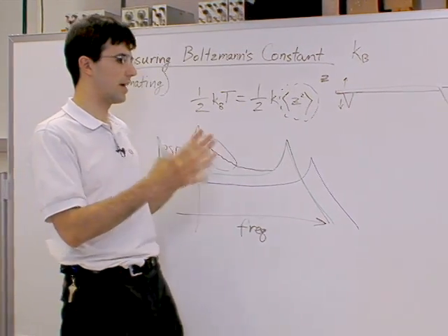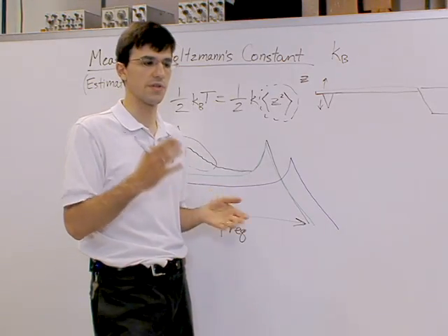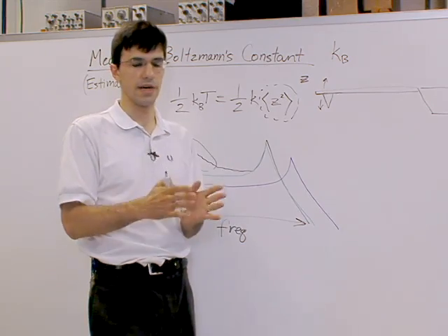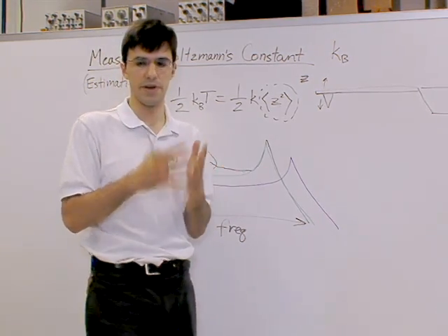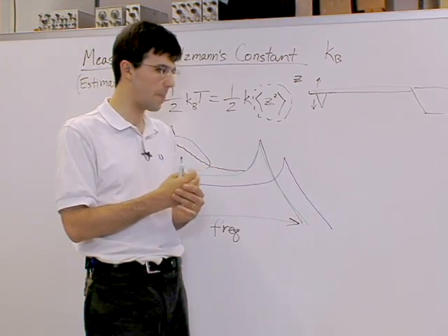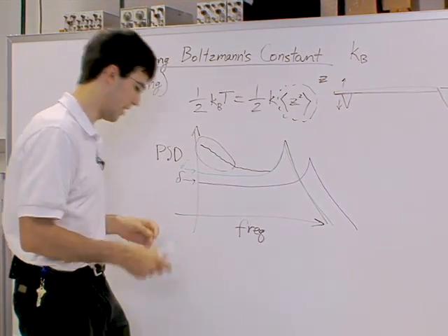You want to have a really nice shape to that force curve. So if you see any non-idealities you want to try to minimize them by adjusting your detector position, your laser focus. Perhaps you might need to change your cantilever if the fingers aren't giving you the best diffractive modes. But you'll want a really nice quality force curve which you can then use to calibrate the value.